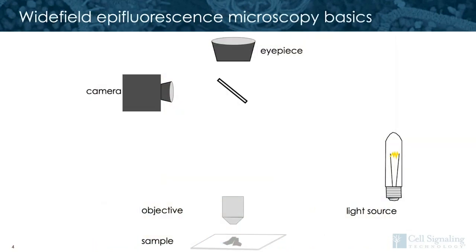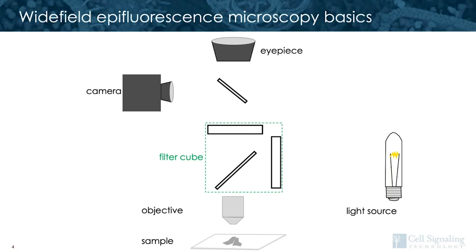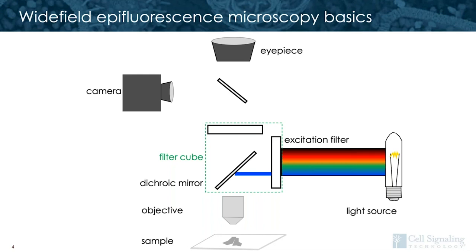Now let's talk about the basics of operating a wide field epifluorescent microscope. You may recall from the previous IF Learning Lab Live that we talked about filter cubes. I want to remind you to learn about the filter cubes on your microscope, because the specs for these are not standard across all microscopes. An epifluorescent microscope relies on a light source which gives light across the spectrum. This light will be gated by an excitation filter to a smaller wavelength, which will excite your sample. Light of a further wavelength in the spectrum is emitted by the fluorophores excited in the sample.